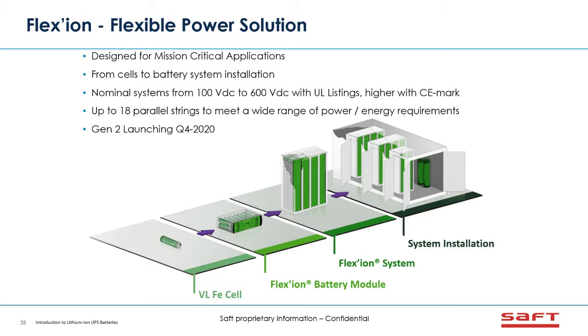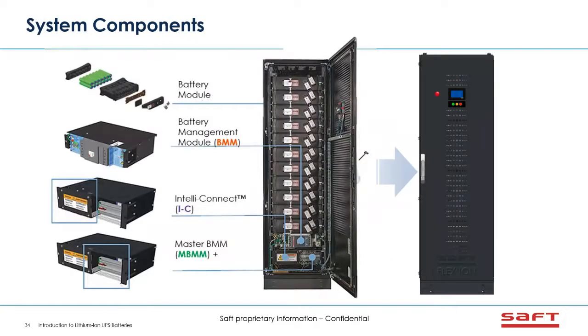And then right around the corner for us is our Gen 2 launching, and I'll talk about what that is in a little bit. There's 4 main components of our system. The battery module, it has 14 large format cylindrical cells, a bus bar, and also an SMU card. Then we have our BMM, which is the battery management module, the IntelliConnect, which is really the power box or power connectors of the string. And then finally, when you have multiple strings working together, we have a master BMM that really just acts as a communication gateway for our system. And you can see it has a built-in HMI display as well. So everything is visually available right from the front of the cabinet.